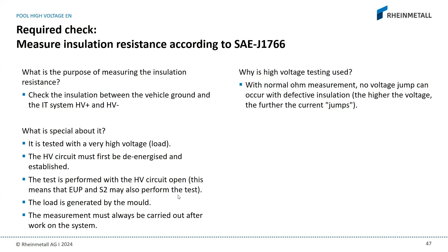To generate this load, we need a special tool. The requirement is a megohmmeter, because if you use a multimeter, you can do a resistance test as well, but you're not able to release 1000 volts, or respectively 400 volts, with a multimeter. This tool is able to generate up to 1000 volts.